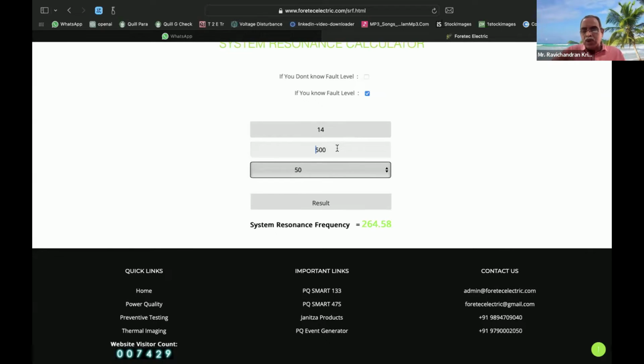All electrical engineers should understand how to calculate the resonance frequency. Suppose, for example, the plant already has only 300 kVAR. So this is 341. If they switch on some capacitor or increase the capacitor, the seventh order can be reduced. So this is simple, no need of any filter. For example, if they wanted to add 100 kVAR, 200 kVAR, see this, 200 kVAR I am adding. Now it is 500 kVAR. For the electrical engineer or electrician using this, it is going to be a fatal accident. Sometimes a fatal accident can happen because it is closer to the fifth order frequency.